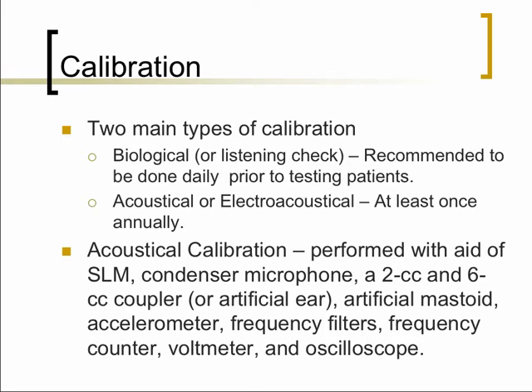And this is the kind of calibration that you're expected to perform on any given day that you will be seeing patients in your clinics. The second, more detailed calibration is what we call an acoustical or electroacoustical calibration, which is required by federal and OSHA laws to be done at least on an annual basis. Of course, if you have a very busy clinic where you're seeing a large number of patients, and if there are more restrictive mandates like federal mandates, you might have to do it more often than annually.